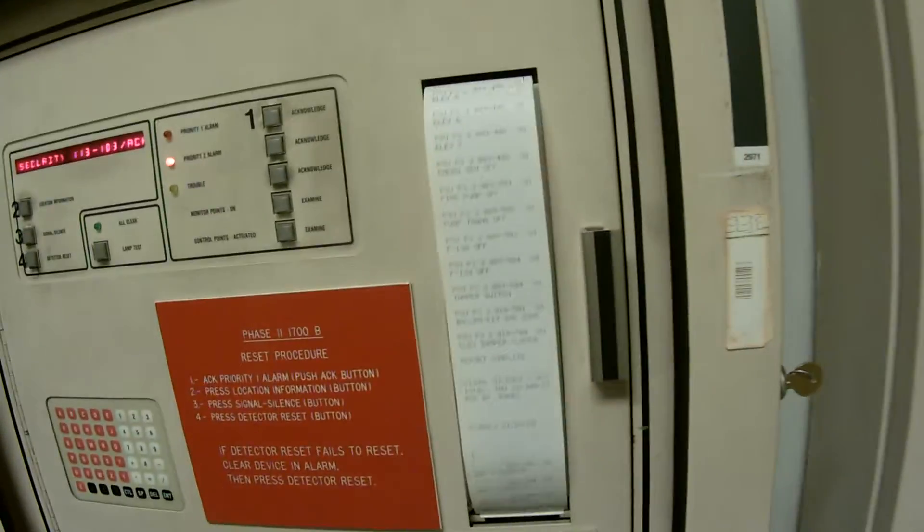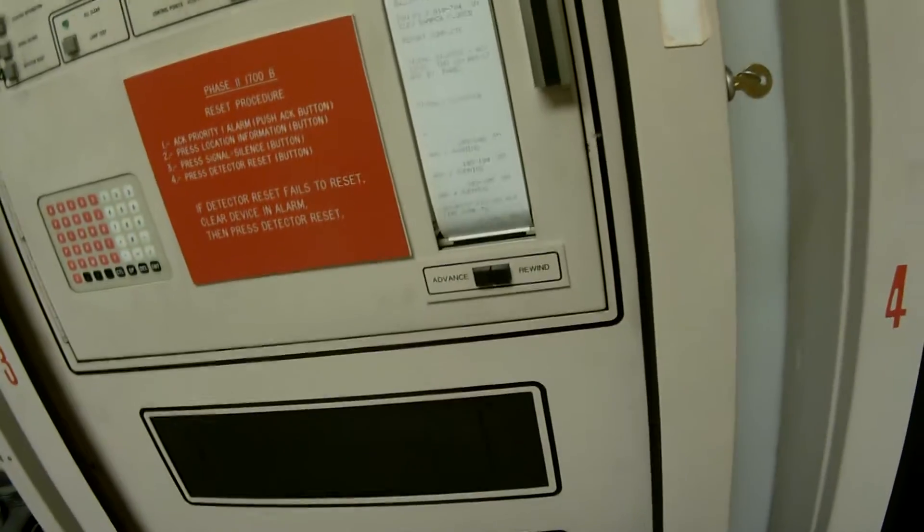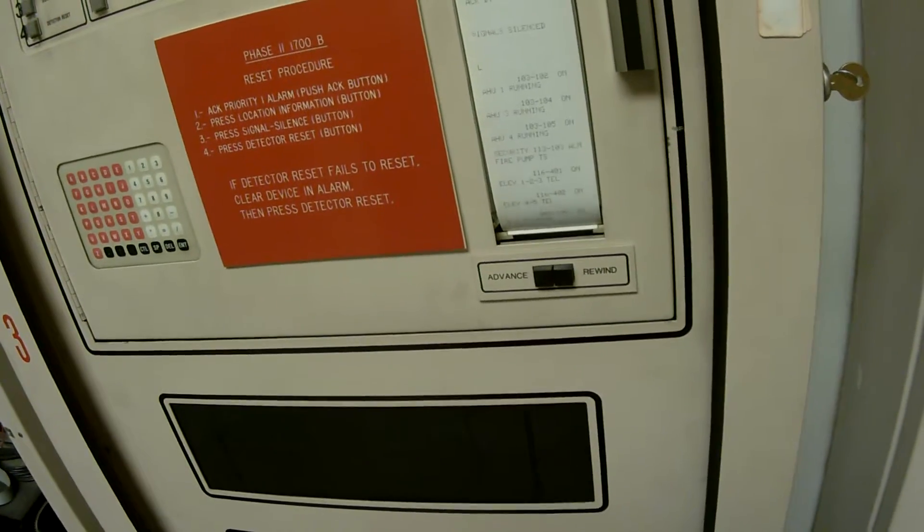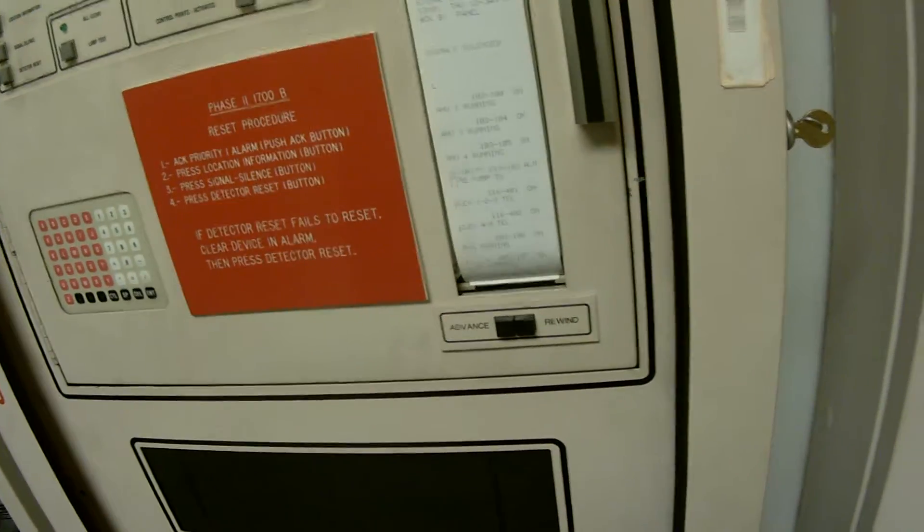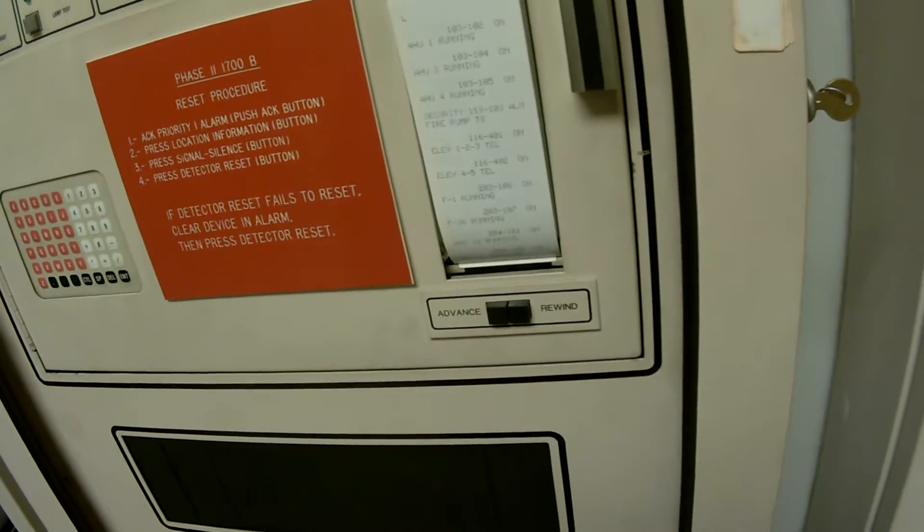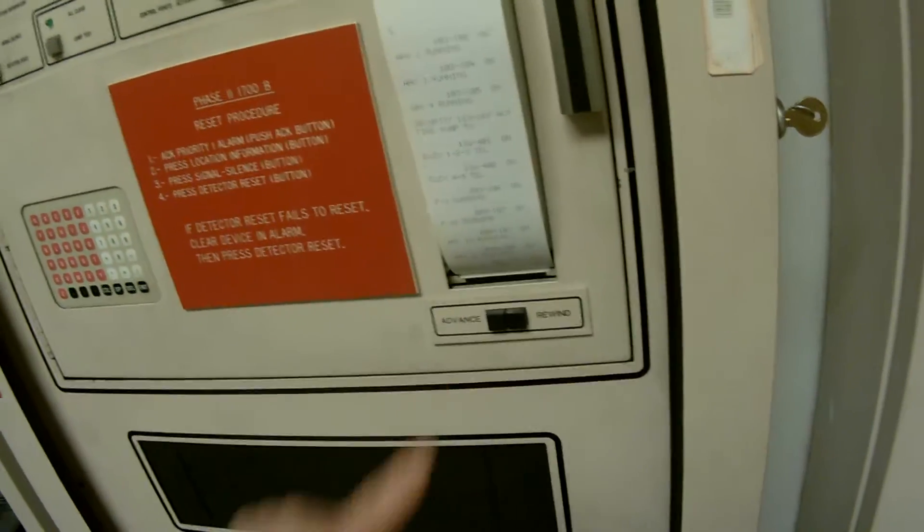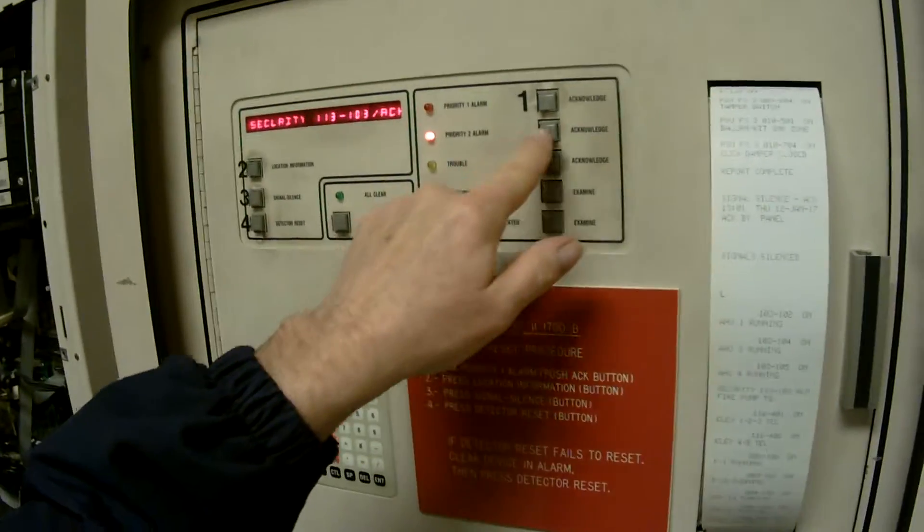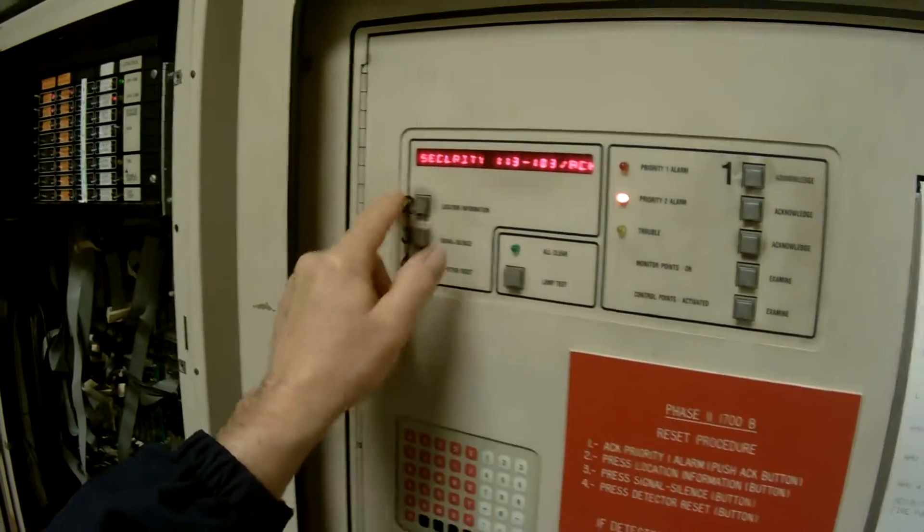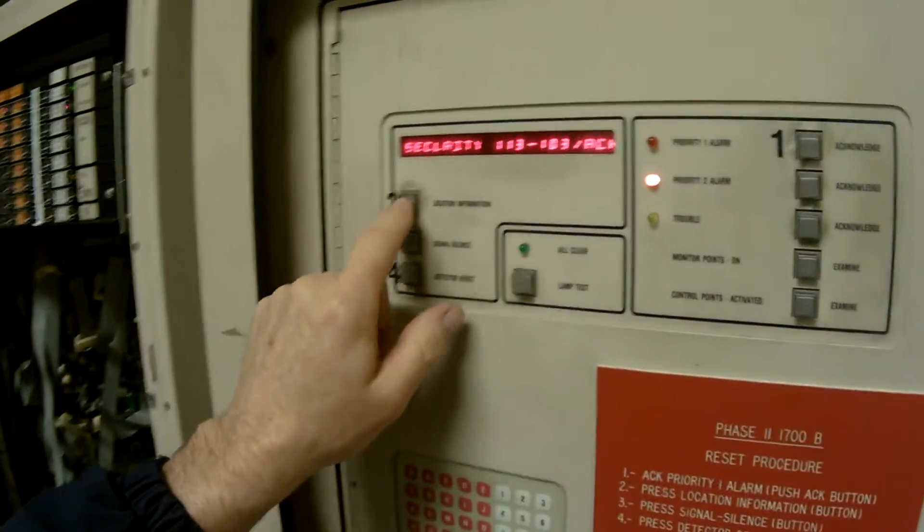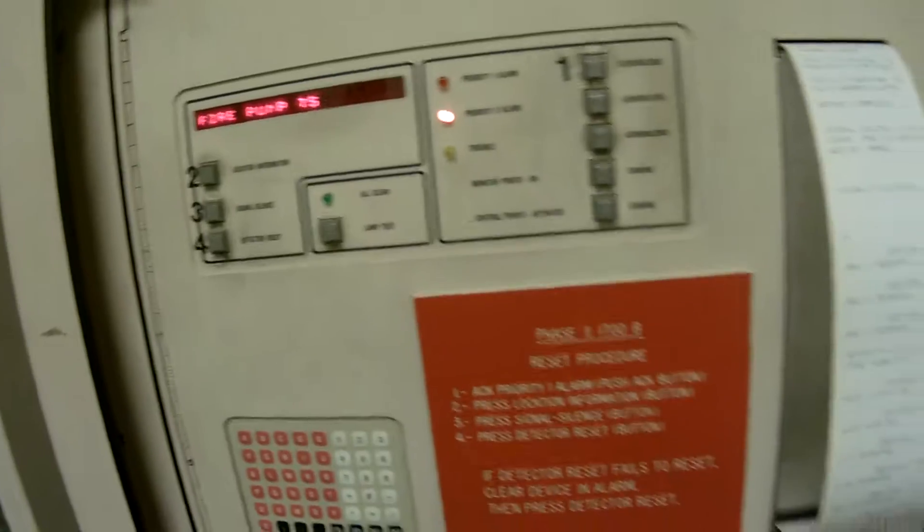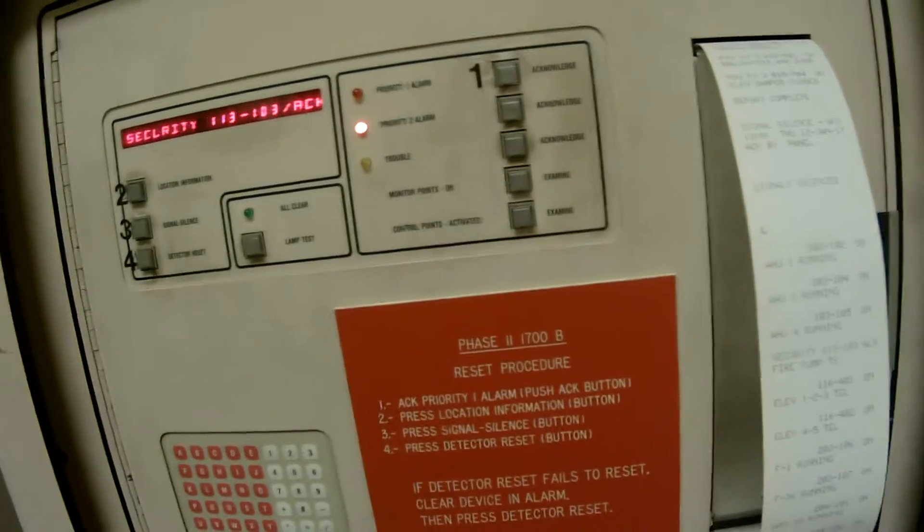And the paper would run out. Now of course, this is going to tell me everything that's on. Looks like we got some air handlers running. Oh, we have a problem with the fire pump tamper switch. I believe that's exactly what that is, right there. We can hit location information - fire pump tamper switch. That's what our priority 2 is.